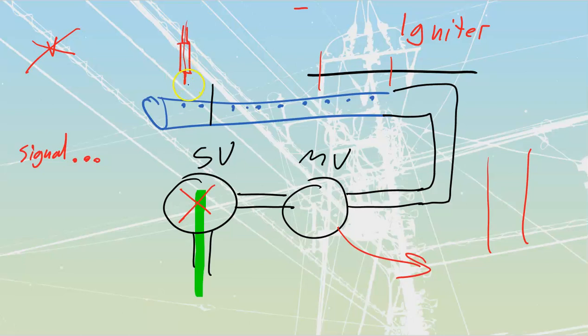What you need to make sure of, first of all, is that these things are close enough. In a lot of cases, the metals will once again warp. Make sure they're directly over top of an orifice as well, that they haven't moved over top. And make sure that orifice is clean, because if there's no gas able to make it out of that orifice, then it's not going to be able to ignite anything. So check for all of that. The other thing to check is your cables themselves. If the cables get a little bit pinched over time, they can actually arc out through the side of these cables, because it's high voltages we're using for them. Adjusting the spark gap is really the biggest thing.